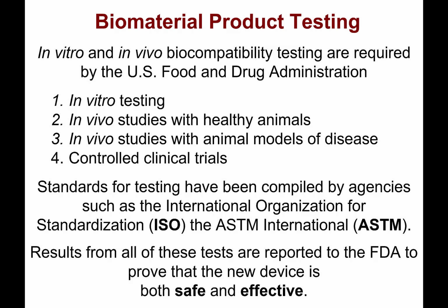And all of this testing must be done under rigorous methods, following guidelines set forth by the International Organization for Standardization, or ISO. We've learned a little bit about the ISO standards, so ISO 10993 and all of its subparts. And then there's also ASTM International, which provides some standards for medical device testing as well. But with all of these tests, what you're really trying to do is build a case to the FDA that the new device is both safe and effective. So safety and efficacy are the two primary concerns of the FDA when they're evaluating medical devices.